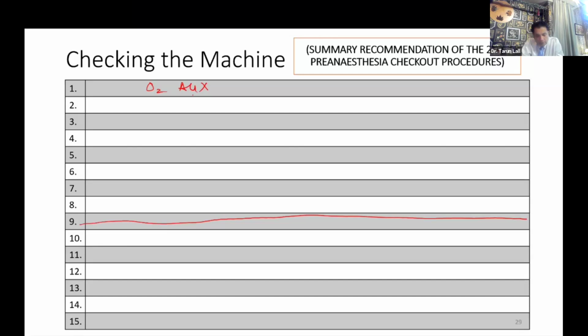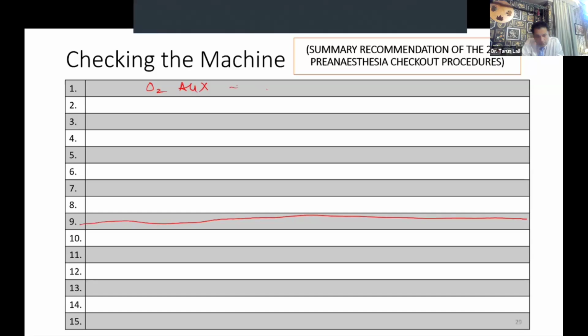So that is the auxiliary oxygen, which should be available with a mechanism for ventilation with a self-inflating bag, so that this oxygen can be provided to the patient in case everything else fails. So auxiliary oxygen plus Ambu, we can say, is your first step. Second step is suction. So these are the two steps which we have done even before I have touched the machine. Then as I touch the machine, the first intuitive step is you turn the machine on, see whether all the electricals are working or not.